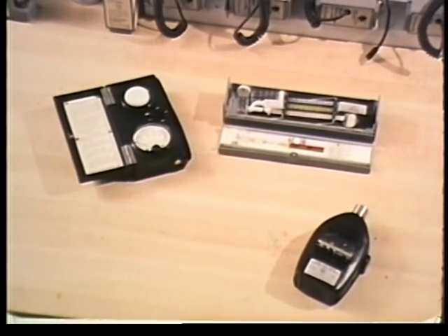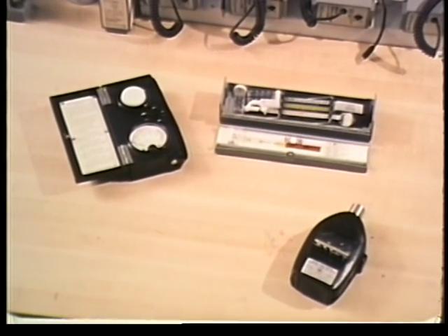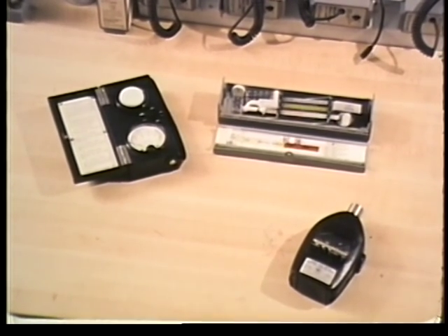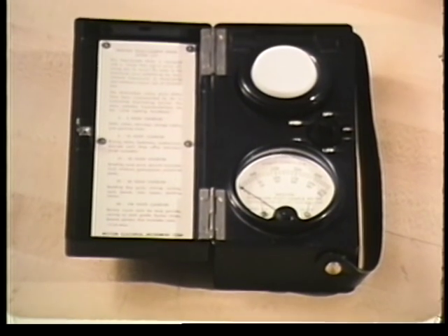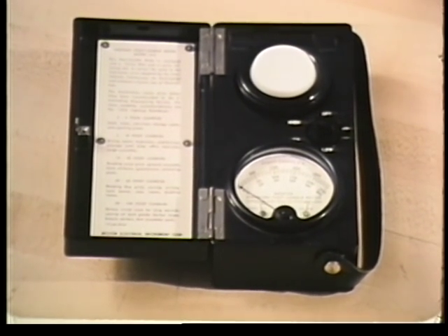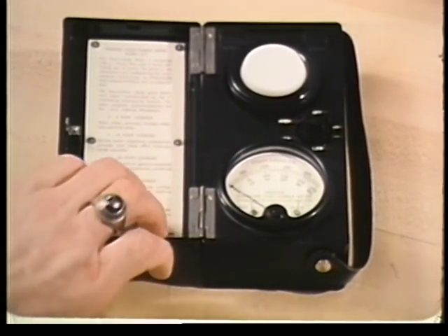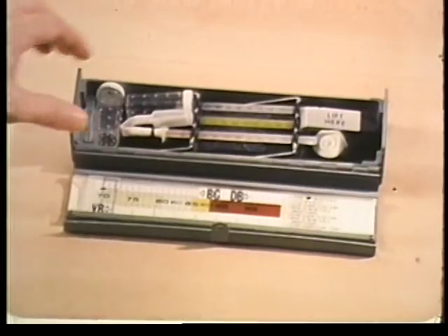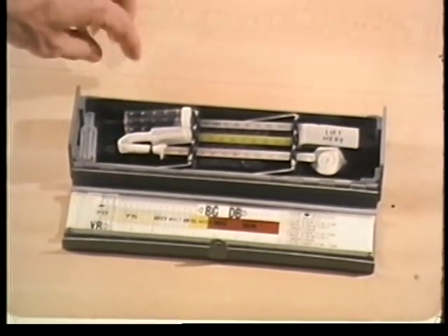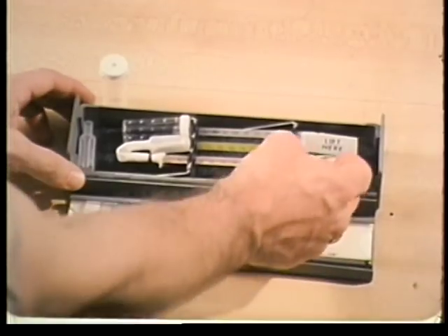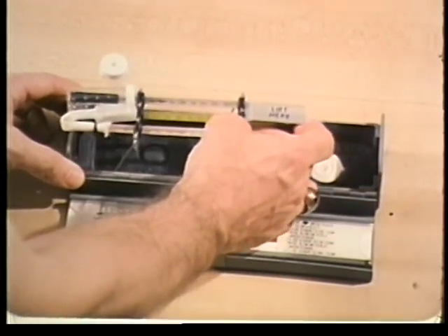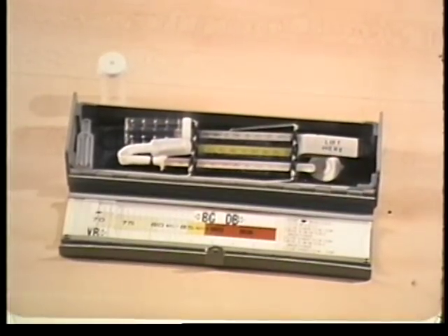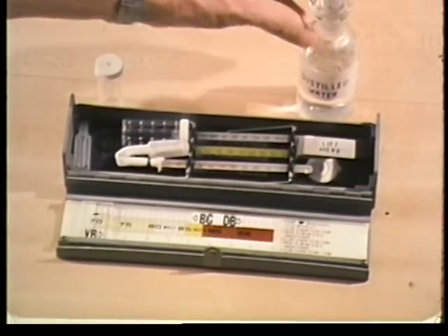Neither of the other two instruments that will be used today require much in the way of pre-survey checkout. The light meter measures, in foot candles, the quantity of light striking the meter. For the wet bulb globe temperature kit, all that's required is making sure the thermometers are in working order and bringing along a small quantity of distilled water.